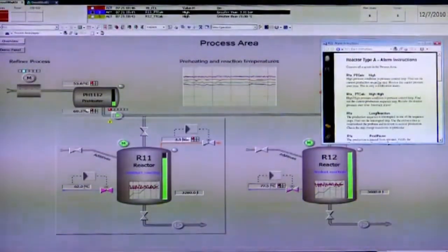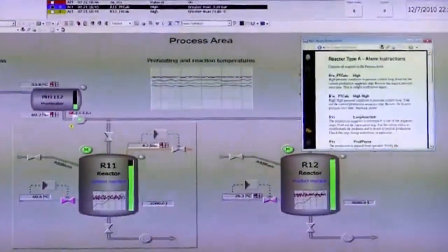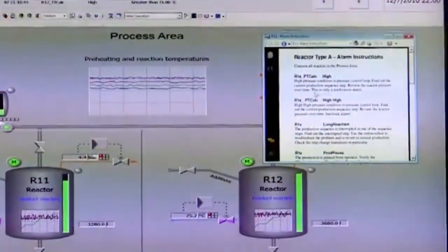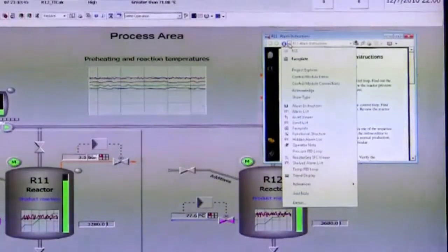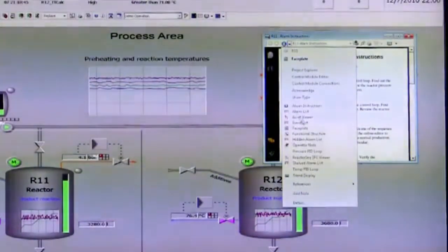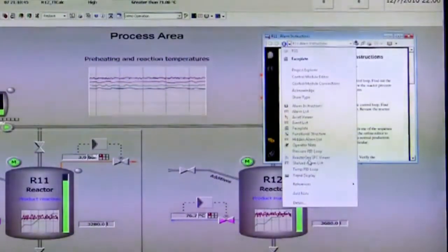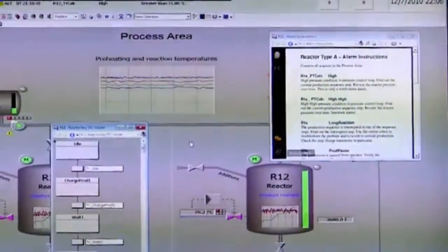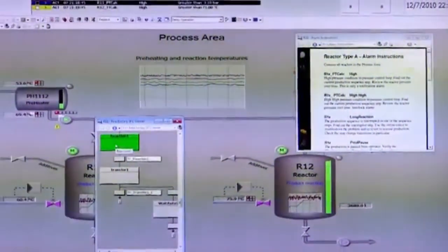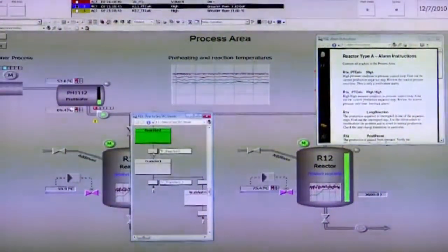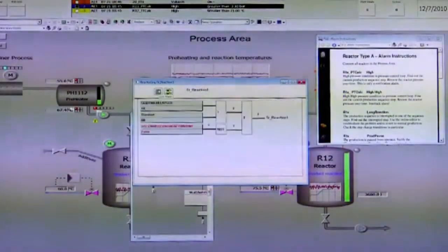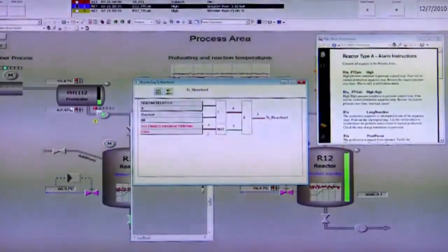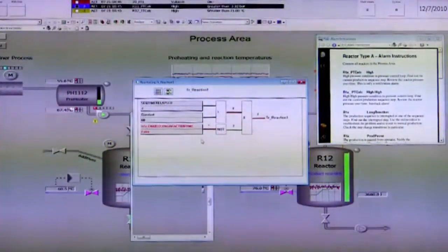In this case, it's having us actually find out the current production sequence step. So instead of having to go to some other screen or other view, here we can just do the pull down list, get the aspect view for this reactor, and then move down to the SFC viewer. It gives us our sequential function chart status. From here we can just double click and see what's holding us out from hitting the next step, and have some various views to help us determine what's holding us out.